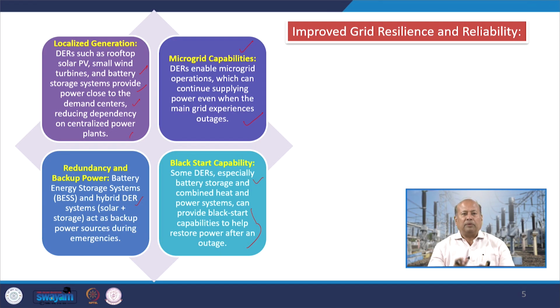So, after having integration of DRs, we can have localized generation, because in a distribution system when you locally inject some source, that will not only enhance the voltage capability at that end node, but the power being drawn from the transmission system or high voltage distribution system to the consumer end will now be reduced, and because the power flow is reduced, indirectly the system loss also will be significantly reduced. So, that is why the integration of DR is going to not only help in reducing carbon, sulfur dioxide as well as NOx, but it can also reduce my system losses.